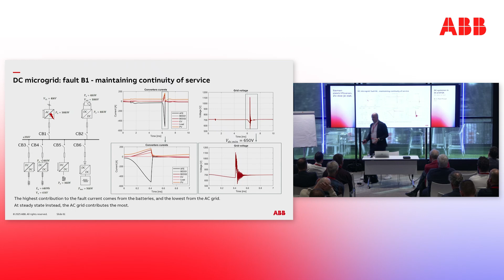Instead, if you use a solid-state circuit breaker and, for example, set the threshold here at 500 ampere, the di/dt is not that critical or super high, because we have only 700 volts operation and we have the cables, so this damps the di/dt a little bit. What is important for us is to look at the grid voltage. We have the fault, the grid voltage starts to fall, but we interrupt very fast, within microseconds, after detecting the threshold. Then we have some overvoltage because the overvoltage protection is not modeled, but we return back to operation. Essentially, we were able to protect the system from a shutdown and continue the operation from the batteries.